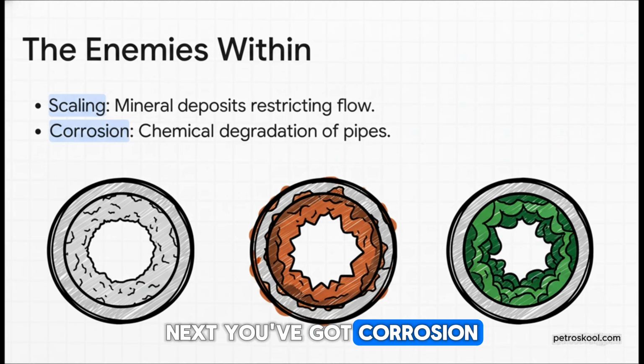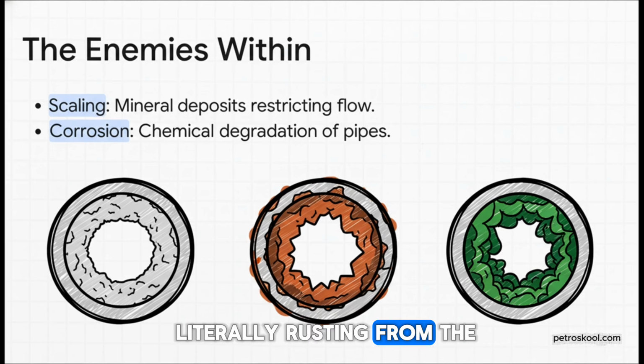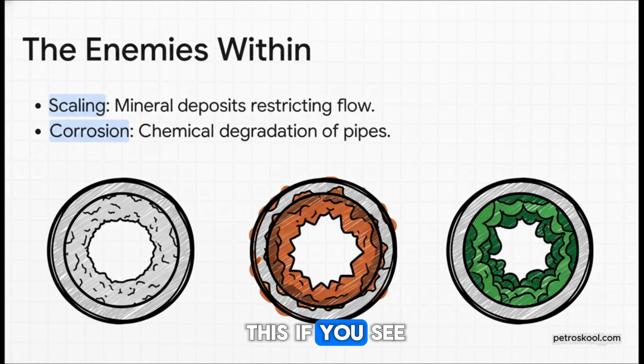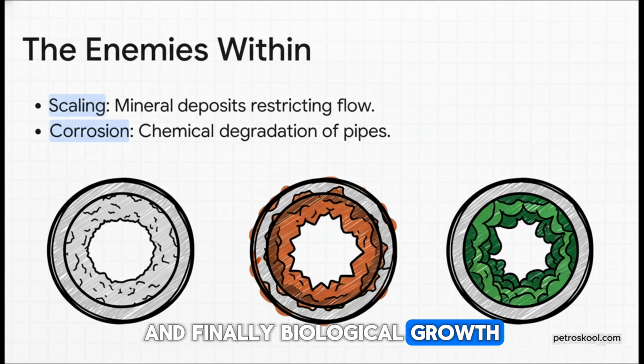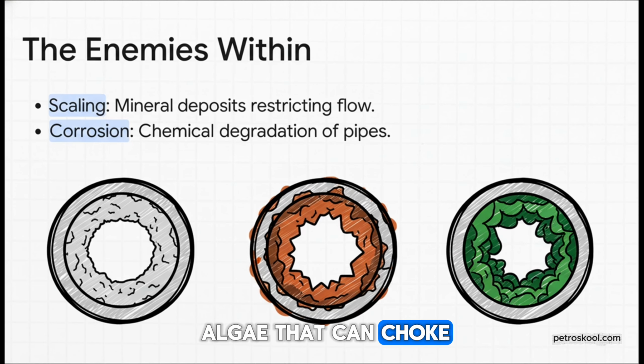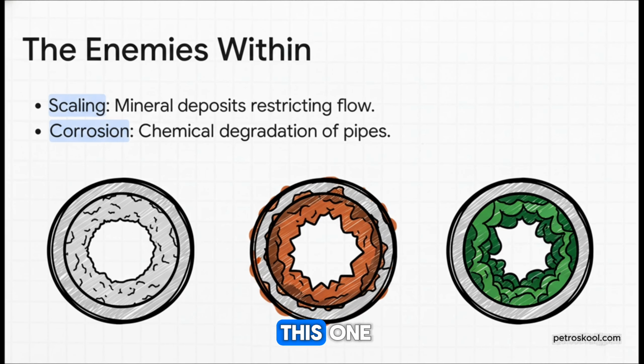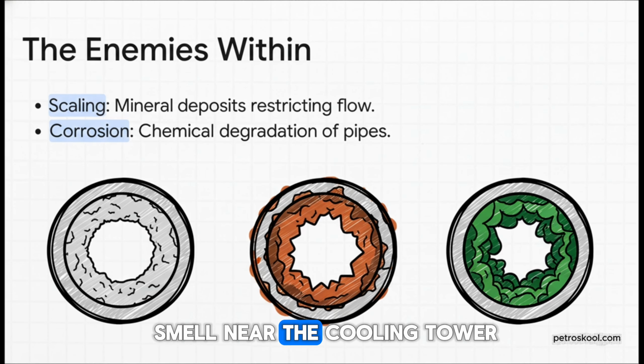Next, you've got corrosion, where the system is literally rusting from the inside out. You can often spot this if you see weird colors in your water samples. And finally, biological growth - we're talking slime and algae that can choke off the flow. A classic giveaway for this one is a musty, earthy smell near the cooling tower.